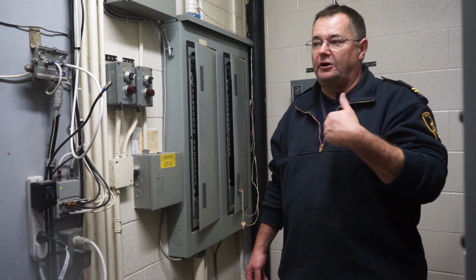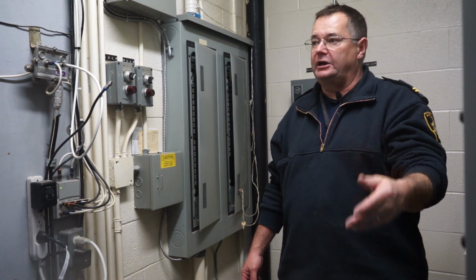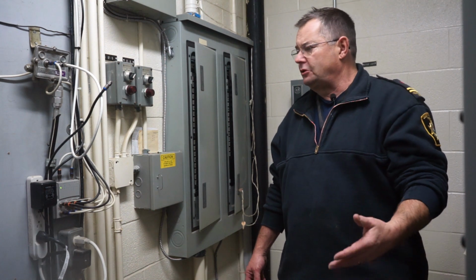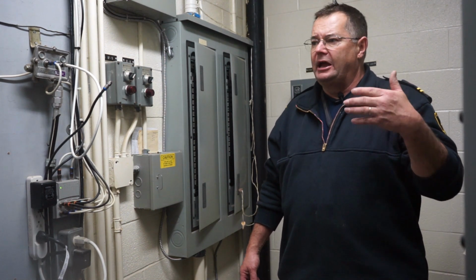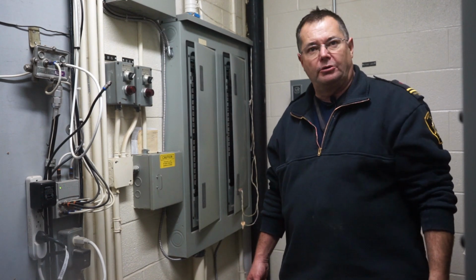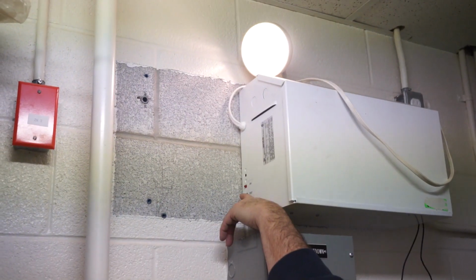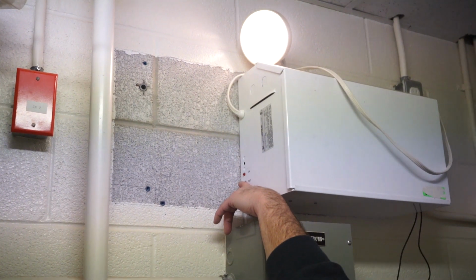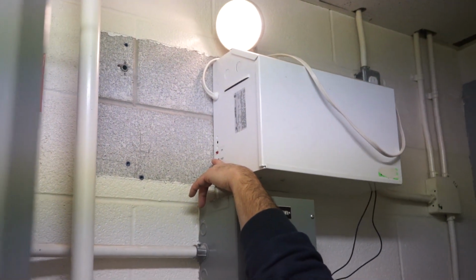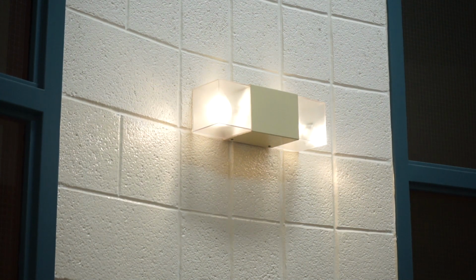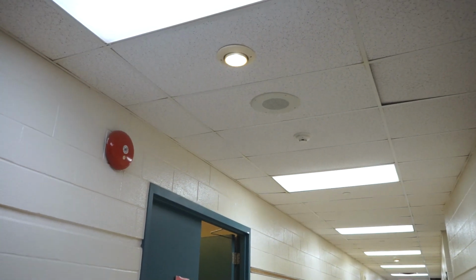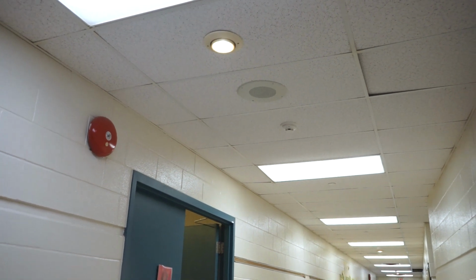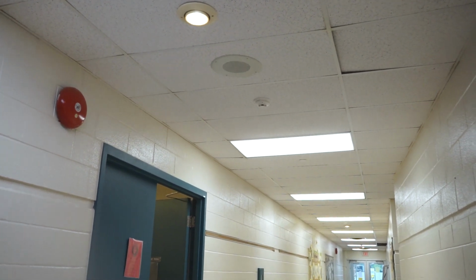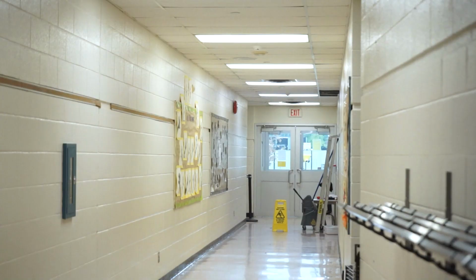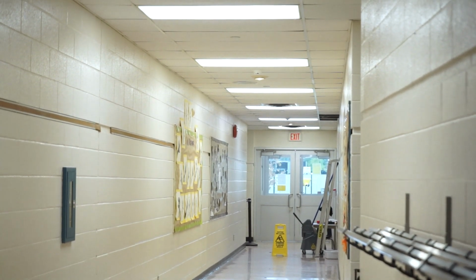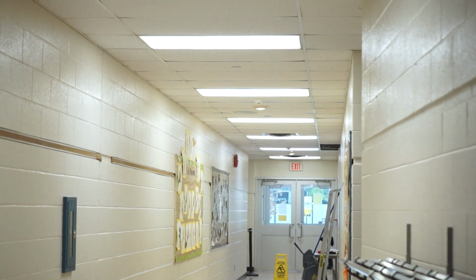We can't have material stored in front. It's not just the fire department coming into your building finding things that we need you to remedy, but it's also a daily, a weekly, a monthly thing that you as the building owner have to be proactive on. Now with this operation here, we are manually turning on the emergency lights. They have to run without power for a minimum of 30 minutes. As we can see here from the power inside the electrical room, all of the emergency lights are what we call pilot lights that are fed off this control box in the hallway. We're actually making sure that these lights work as well.